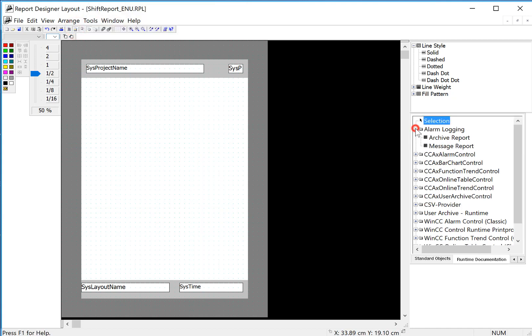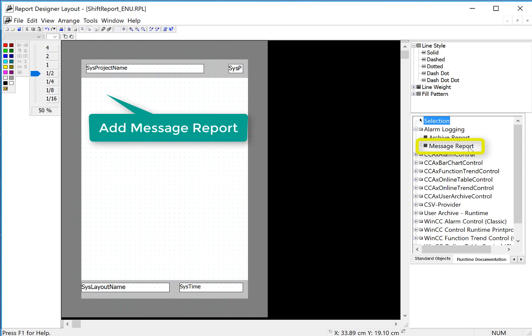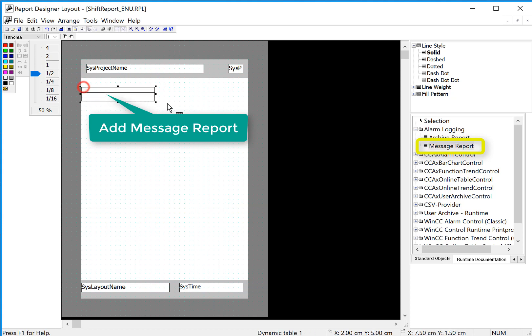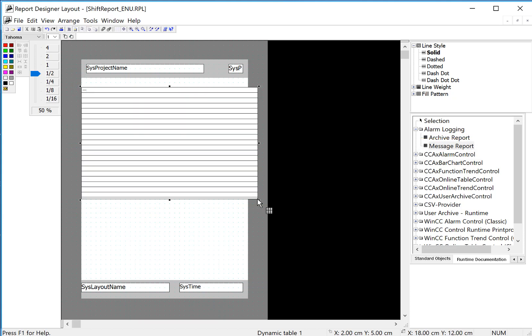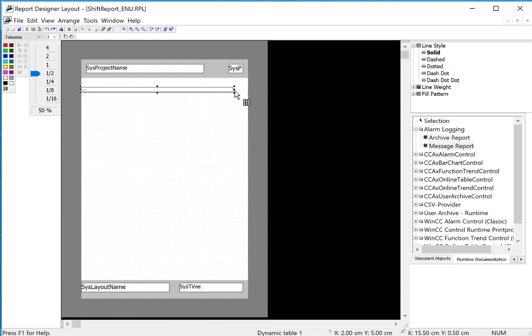I'll go under alarm logging. We have two things here: archive report and message report. Message report are active alarms, archive report are archived messages. So I'll choose a message. These controls are self-paginating. They're going to grow to fit the data, so you don't have to make them big like this.